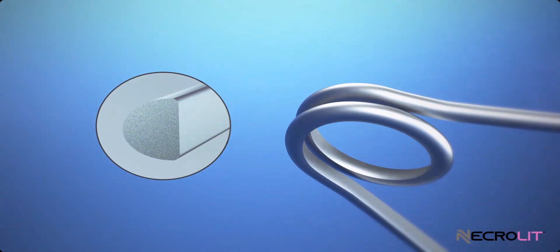A particular basket of equivalent width and length with variable flexibility nitinol wires gives perfect retrieval capacity. The basket has no tip, and the junction in the distal part between the filaments with variable flexibility creates an empty space. This characteristic gives it atraumaticity and adaptation to the cavity object of the recovery of the necrotized tissue. The spiral steel core that connects the handles to the retrieval system deliberately has a small diameter in order to give a rotation called the helix effect, essential to allow the necrotized tissue to detach quickly.